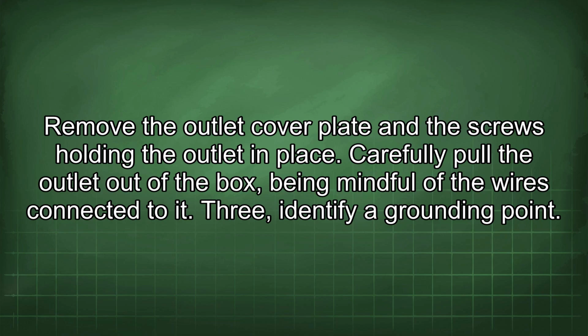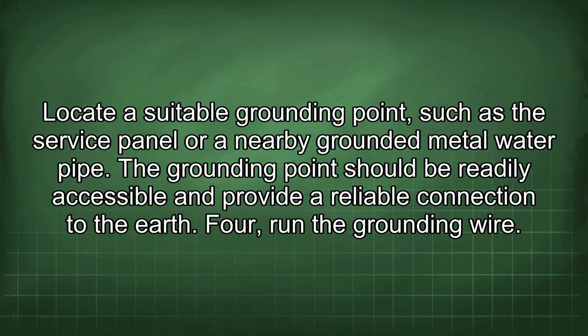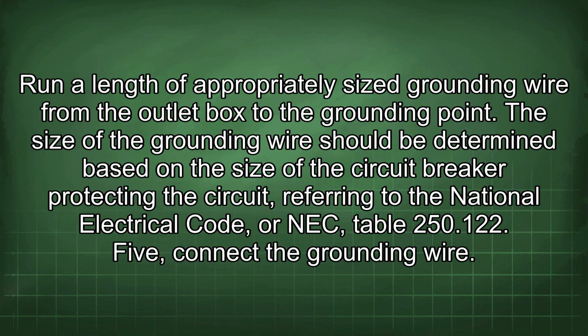3. Identify grounding point. Locate a suitable grounding point, such as the service panel or a nearby grounded metal water pipe. The grounding point should be readily accessible and provide a reliable connection to the earth. 4. Run the grounding wire. Run a length of appropriately sized grounding wire from the outlet box to the grounding point. The size of the grounding wire should be determined based on the size of the circuit breaker protecting the circuit, referring to the National Electrical Code, or NEC, Table 250.122.